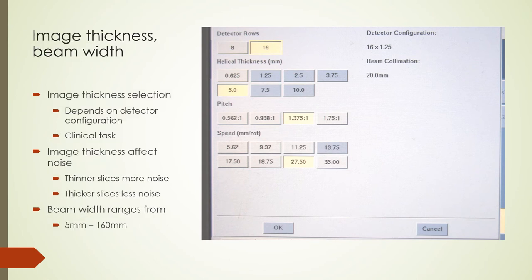Selection of slice thickness depends on the clinical task and acceptable noise level. Thinner slices are noisier than thicker slices for the same dose, since relative noise is inversely related to the square root of the signal source — which can be dose, mAs, or slice thickness. The detector configuration chosen determines the thinnest slice available; for example, a 16 by 1.25 mm configuration allows slice thicknesses from 1.25 mm to 10 mm. Beam width options can range from 5 mm to 160 mm, and wider beam widths allow larger anatomy sections to be scanned per rotation, reducing scan time.